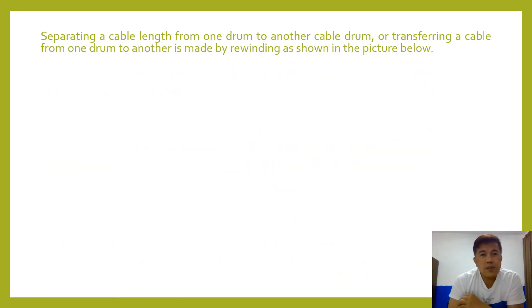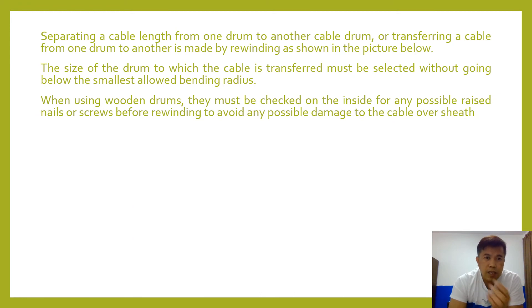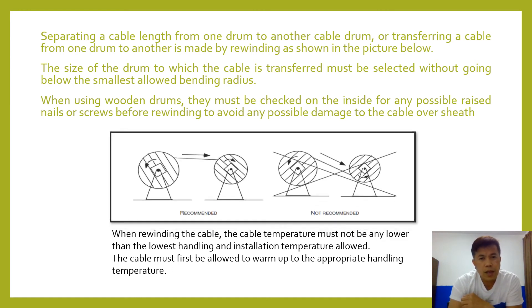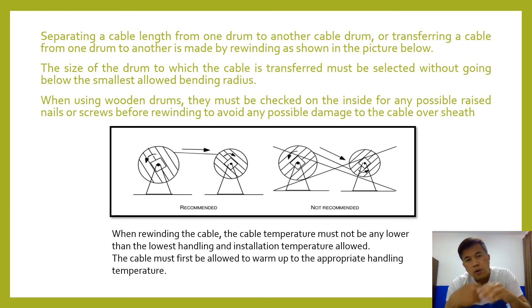Separating the cable length from one drum to another, transferring the cable drum to another drum — rewinding. Check the size of the drum, verify if it is clean, clean the drums, and ensure there are no screws or nails that can damage your cable. This is the recommendation and what is not recommended for how to uncoil your cable drums.